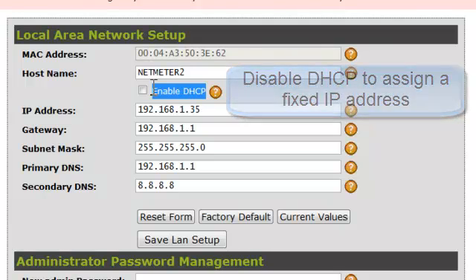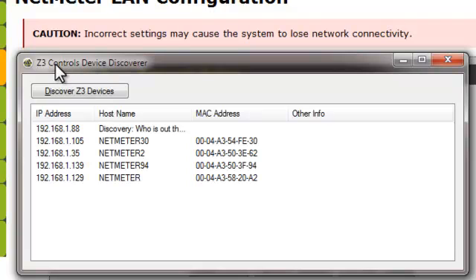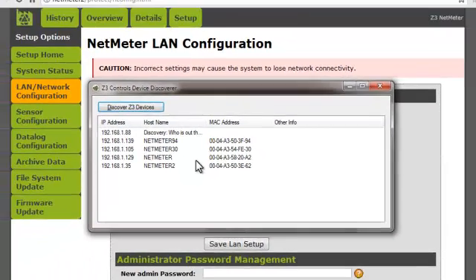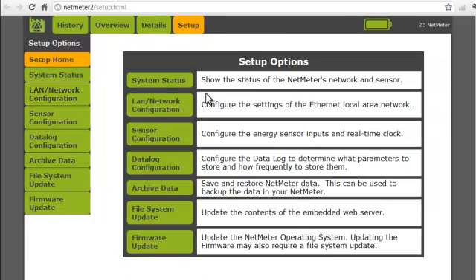When using fixed IP addresses, you probably already know the IP addresses of all the NetMeters in your system. However, if you need to determine what IP addresses have been assigned to each NetMeter, there are several ways to do this. Z3 Controls provides a utility called the Z3 Controls Device Discoverer — a program that you install on a PC. It scans your local area network for any Z3 Controls devices and displays them in a list that includes the IP address. You can download the device discoverer software from the Z3 Controls website. Another method is to simply browse to each separate NetMeter and determine its IP address through the Status page available in the Setup menu.